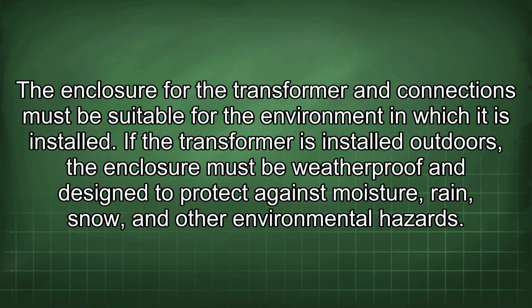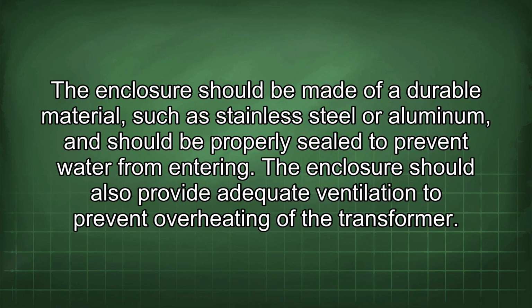The enclosure for the transformer and connections must be suitable for the environment in which it is installed. If the transformer is installed outdoors, the enclosure must be weatherproof and designed to protect against moisture, rain, snow, and other environmental hazards. The enclosure should be made of a durable material such as stainless steel or aluminum and should be properly sealed to prevent water from entering. The enclosure should also provide adequate ventilation to prevent overheating of the transformer.